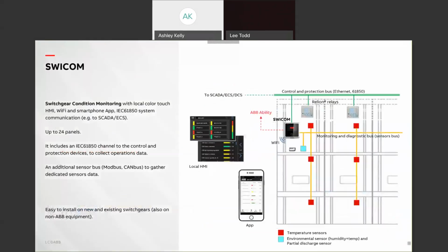So how do we collect all the data to get to one holistic view? SWICOM is one device - a relay mounted to your switchgear that all the relays talk to. All sensors connect to it, giving one point of contact for all digital assets. SWICOM collects data not only from ABB's assets but also from non-ABB assets, regardless of which manufacturer you have for switchgear or relays.